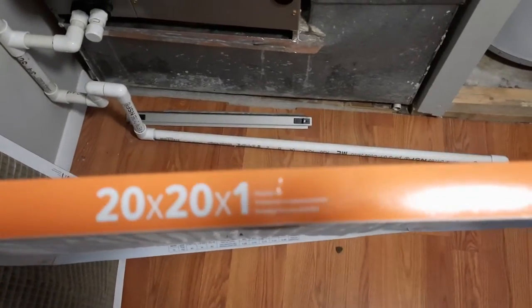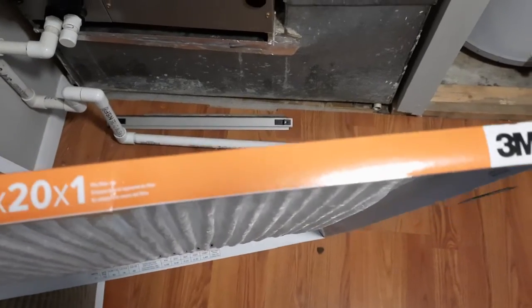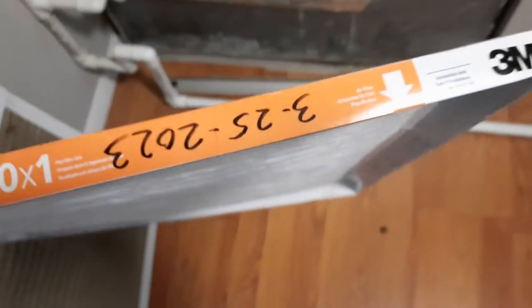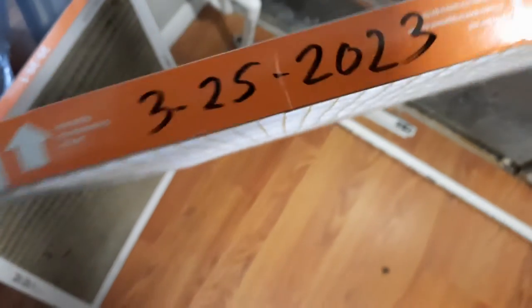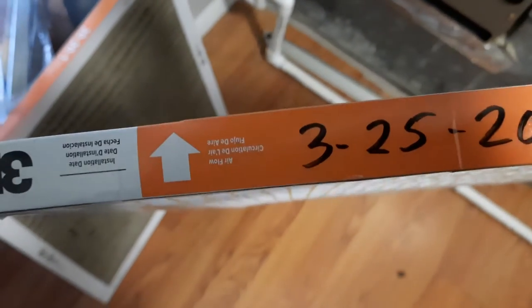The new one is 20x20x1 and the 3M kind. I will suggest anyone doing this to put the date on the side to know when we last did it. Pay attention to the airflow — air goes in this case from the bottom, because air comes from the side, goes down on the bottom, and goes up into the unit.